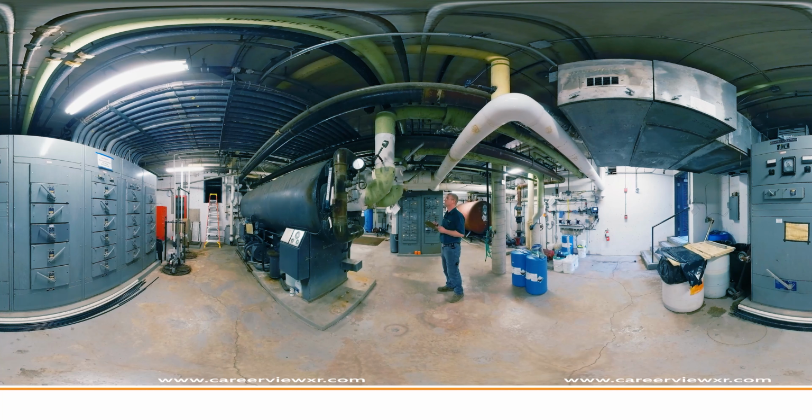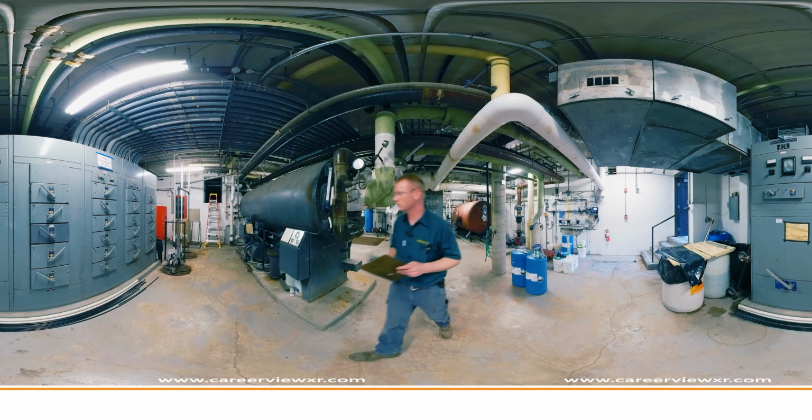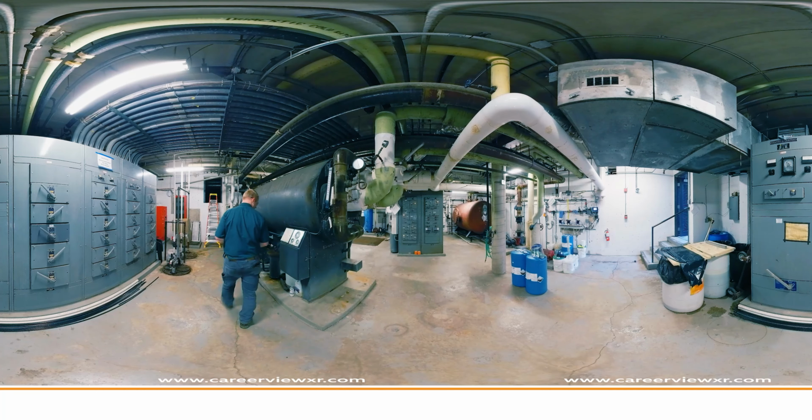Eric is performing general maintenance on the chiller by checking and recording start and stop times and the length of the run time of the machine. Eric purges air out of the chiller and verifies fluid levels and steam pressure. The chiller is connected to the automation system, allowing technicians to check on the machine on their laptops remotely.